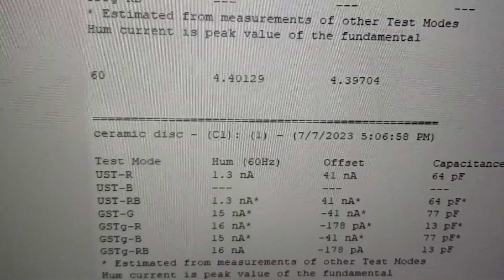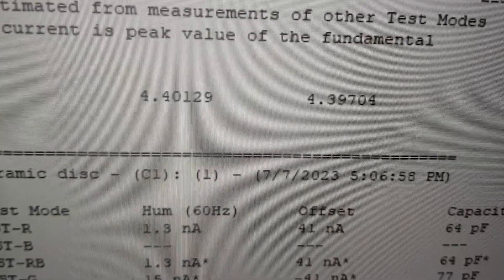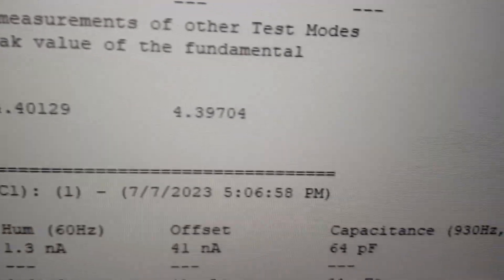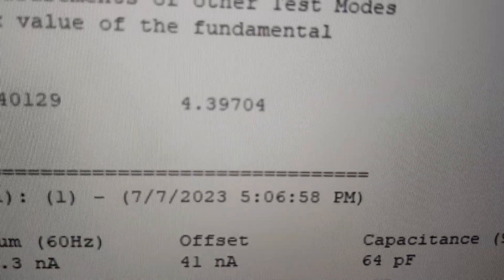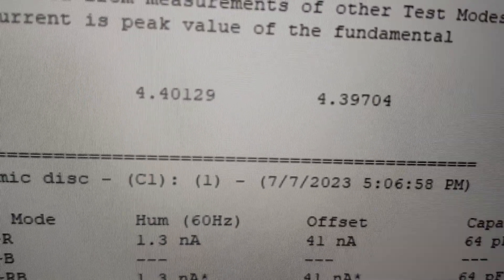When you see the power factor here for the healthy one, it's on top of the dissipation factor — they have almost the same value. If you want to see the actual values, the dissipation factor is 4.4 and the power factor is 4.39. As you can see, they are very, very close to each other.